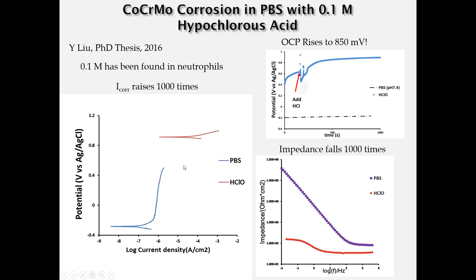Most recently, we've been looking at the role of hypochlorous acid. My PhD student has noted in the literature that people have measured as high as 100 millimolar hypochlorous acid levels in certain circumstances of inflammation. And when you subject cobalt chromium molybdenum to those conditions, this red line shows up. That is, the open circuit potential for cobalt chromium rises to almost 900 millivolts. And the corrosion current is up here about 3 orders of magnitude higher, about 1,000 times higher than when in phosphate buffer. The resistance of the oxide films of cobalt chromium in the presence of this 100 millimolar hypochlorous acid is down about 3 to 4 orders of magnitude. So a dramatic decrease in the resistance of the oxide. Clearly, the presence of this species in the solution is damaging the oxide film, raising the oxidation potential, and moving the alloy up into a very severely corroding condition.